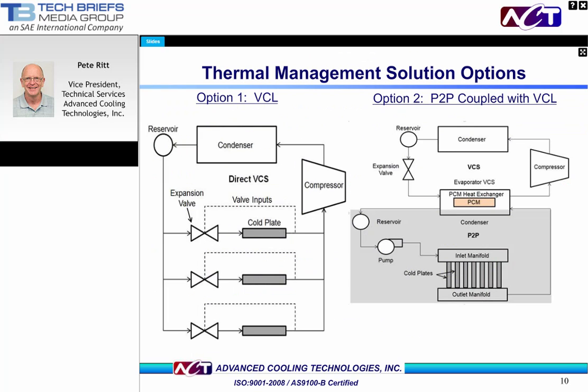Here are diagrams of the single large vapor compression loop, option 1, and the improved combined pump two-phase VCL and PCM, option 2. The pump two-phase portion is highlighted in gray. In the single VCL solution, each electronic board requires an electronically controlled expansion valve, likewise requiring a variable frequency drive compressor. The pump two-phase system can use a single manifold to feed all of the boards, reducing both weight and complexity.